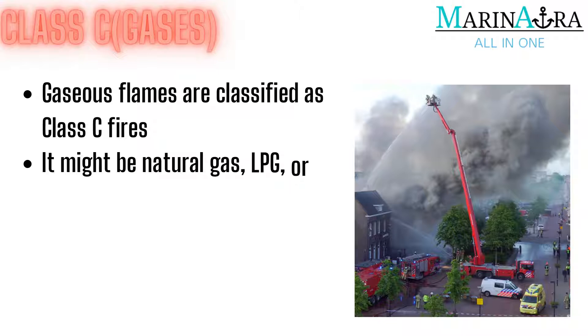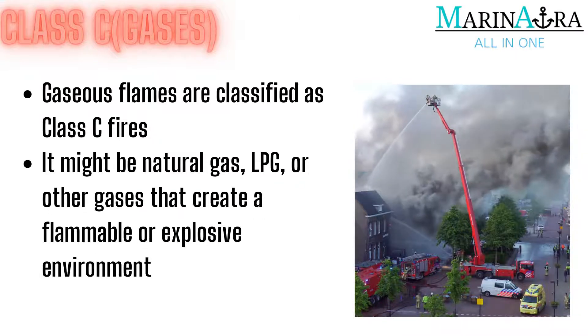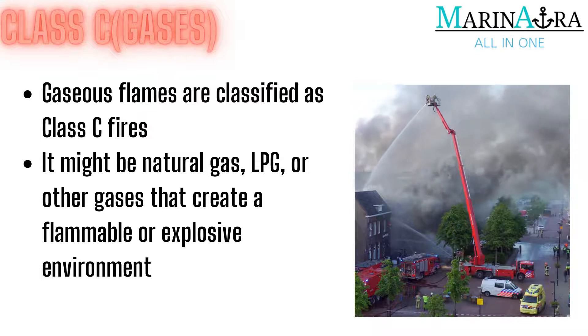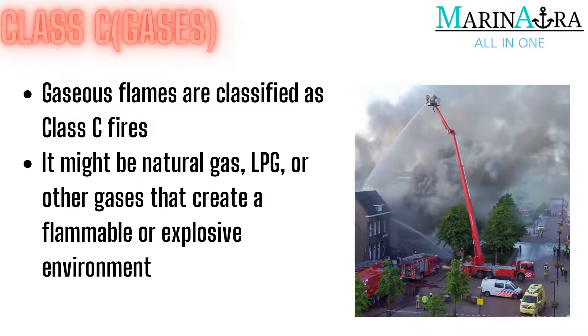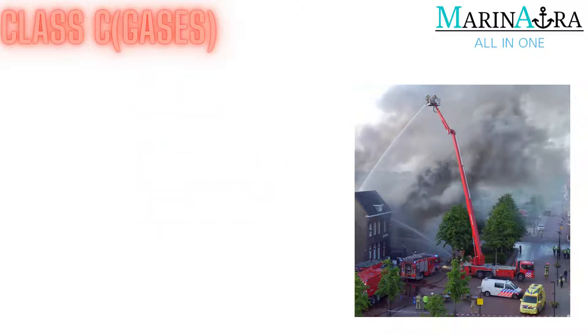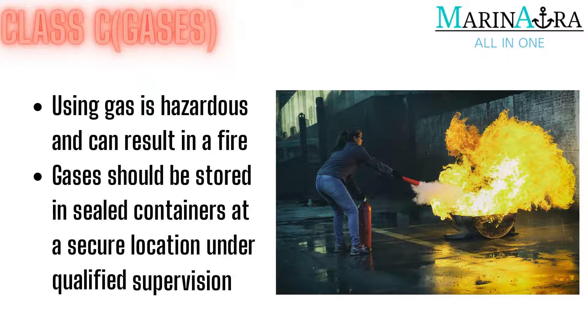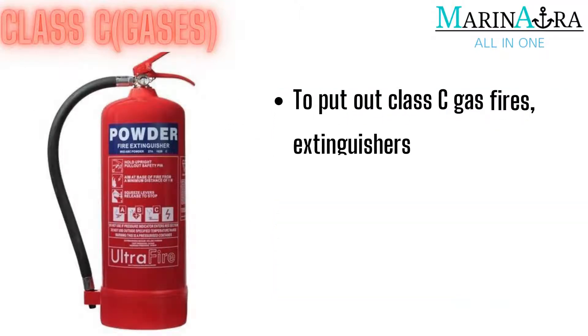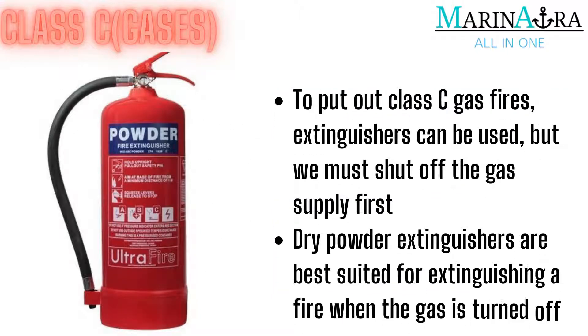Class C — Gases. Gaseous flames are classified as class C fires. It might be natural gas, LPG, or other gases that create a flammable or explosive environment. Working with gas is hazardous and raises the chance of a fire. Keep stored gases in sealed containers in a secure storage facility, and make sure gas work is done by qualified individuals. While extinguishers can be used to put out class C gas fires, the only safe way to do so is to turn off the gas supply. A dry powder extinguisher is the best type of extinguisher for putting out a fire when the gas supply is shut off.